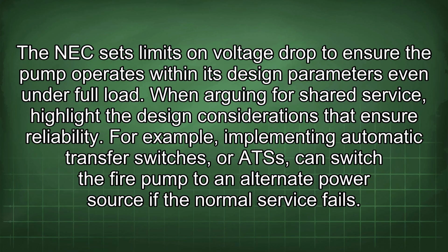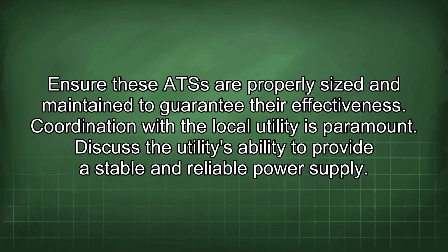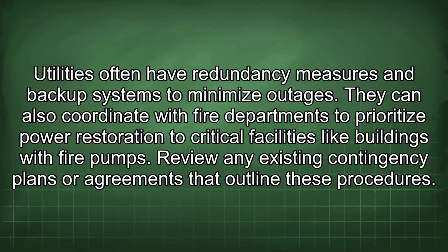When arguing for shared service, highlight the design considerations that ensure reliability. For example, implementing automatic transfer switches, or ATSs, can switch the fire pump to an alternate power source if the normal service fails. Ensure these ATSs are properly sized and maintained to guarantee their effectiveness. Coordination with the local utility is paramount. Discuss the utility's ability to provide a stable and reliable power supply. Utilities often have redundancy measures and backup systems to minimize outages. They can also coordinate with fire departments to prioritize power restoration to critical facilities like buildings with fire pumps. Review any existing contingency plans or agreements that outline these procedures.